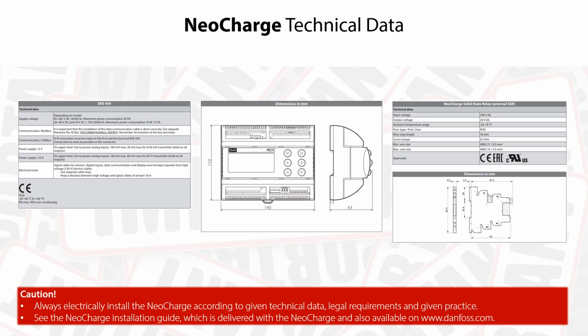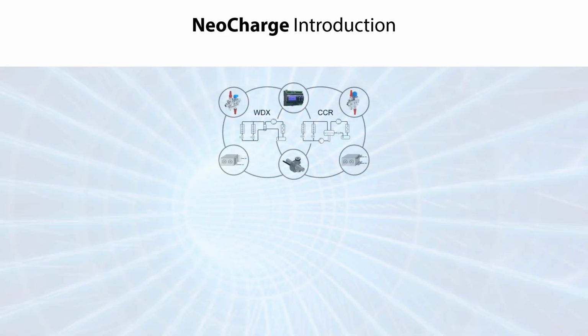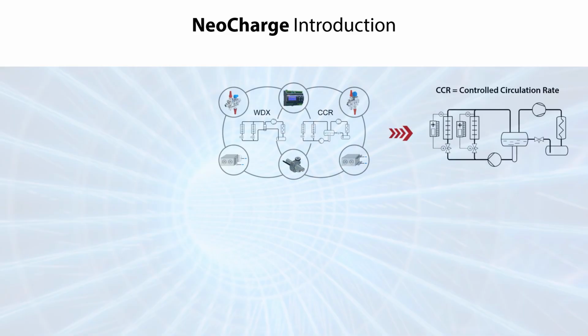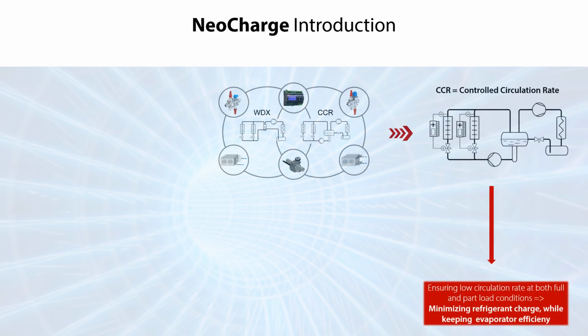Danfoss.com. The Danfoss Neocharge is a complete solution for controlling refrigerant injection into industrial evaporators. The Neocharge addresses two main applications. One application is controlled circulation rate systems, also called CCR systems, which essentially are traditional pump circulation systems. Here, the Neocharge ensures that the circulation rate is kept low at both full and part load conditions, thereby minimizing the refrigerant charge while keeping the efficiency of the evaporator.